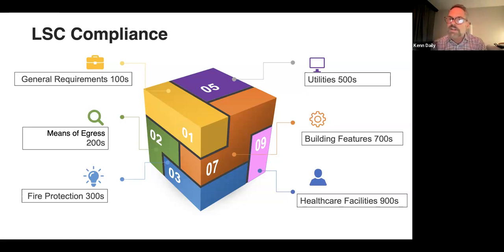Now that is all the healthcare facilities book. So if you've ever thought where this all comes from, NFPA 99 is healthcare facilities. And that's the book that any of us who are certified as healthcare entities, who then have to follow chapters 18 and 19 of NFPA 101, then the healthcare facilities book applies to us. And that's systems issues. It's based on risk. It's a little different guide or book than other life safety books, but we'll talk about that as we get down to the 900 series tags, like things like electrical and oxygen use and those types of things.